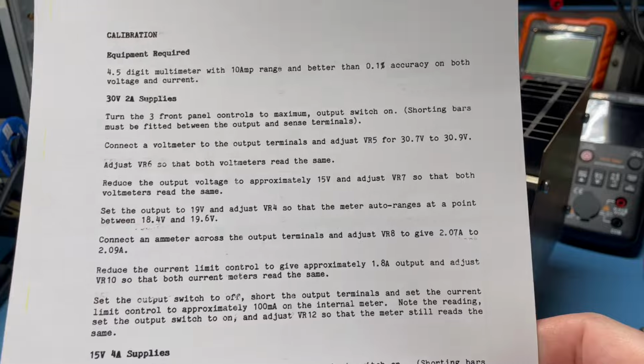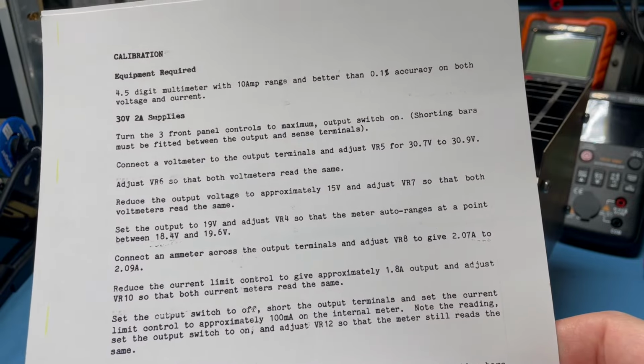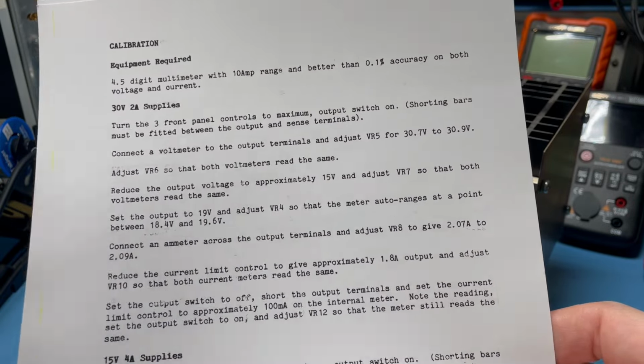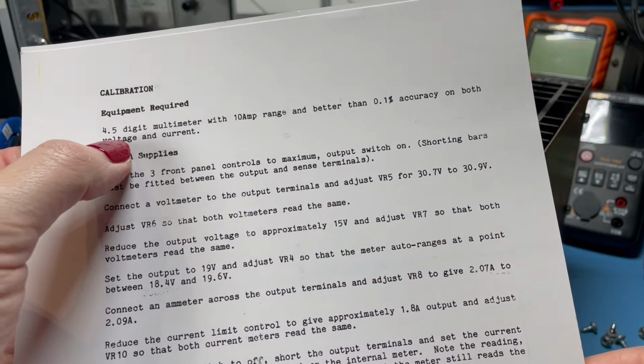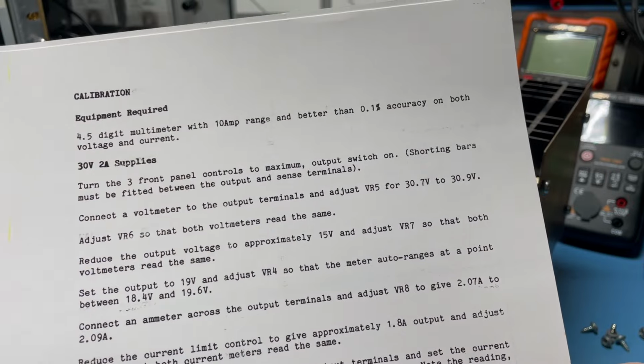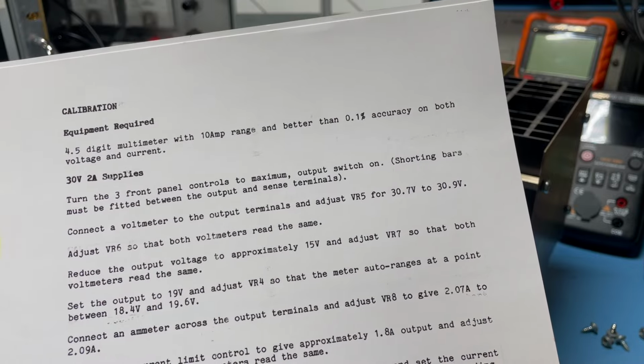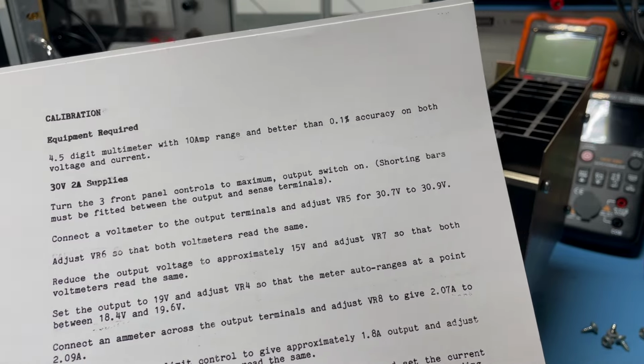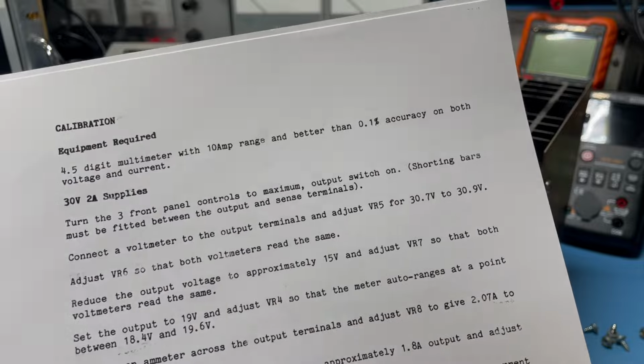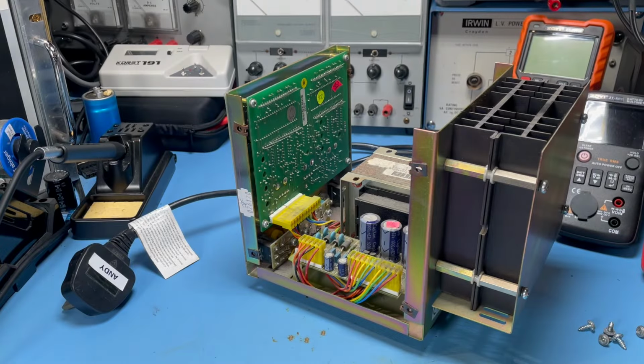Okay, so calibration on this power supply seems pretty simple. You require a 4.5 digit multimeter with a 10 amp range and better than 0.1% accuracy on both voltage and current, and I believe a bit of patience. Well, that's not a problem, I've got both of those things.